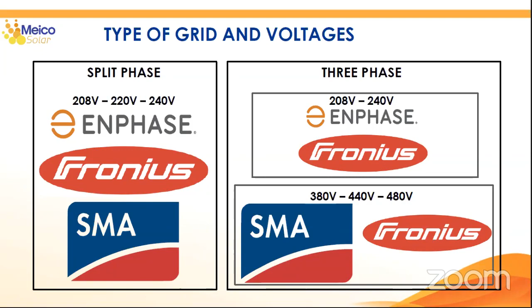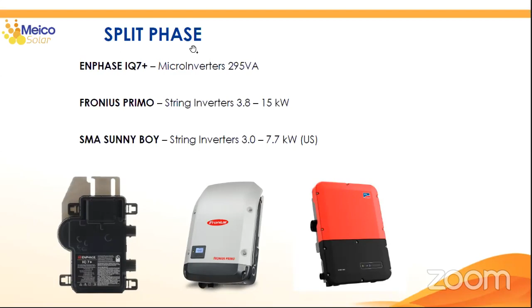Let's start with the split phase. In this solution we have three types: the ENPHASE IQ7 microinverters, shown in the bottom left; the FRONIUS Primo family of string inverters, with different powers from 3.8 kilowatt to 15 kilowatt; and the SMA Sunny Boy family, also string inverters, from 3 kilowatt to 7.7 kilowatt. This is only the American versions, we also have European versions with different powers, but we'll talk mainly about the US versions. These are the three solutions for the split phase grid.